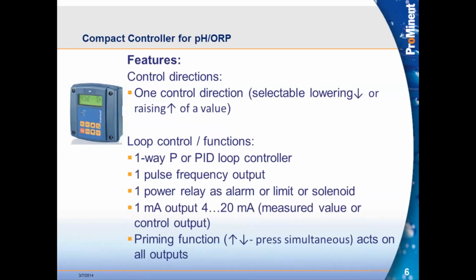As I mentioned, it is a little bit more basic. The control direction is one direction only, meaning you can select increasing pH. In that case, your pump would be feeding a caustic solution, so you're going to go up in pH, or not at the same time, you can lower the pH by feeding an acid. Okay. For ORP, you could add an oxidant and then something to remove that oxidant. So, for example, chlorine, you can increase the chlorine reading.